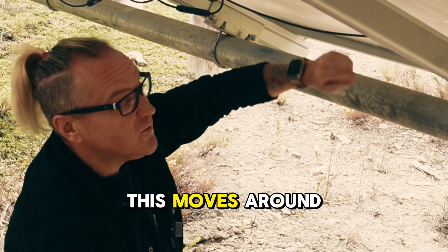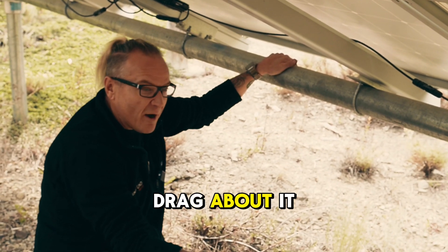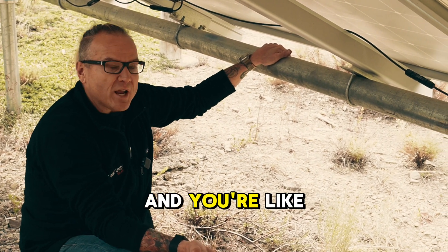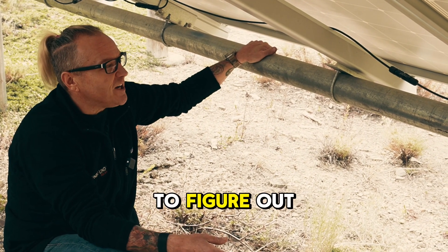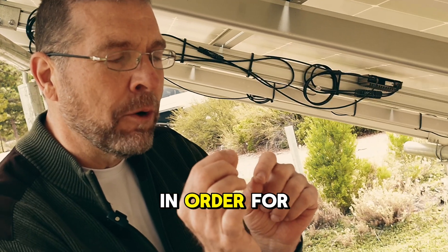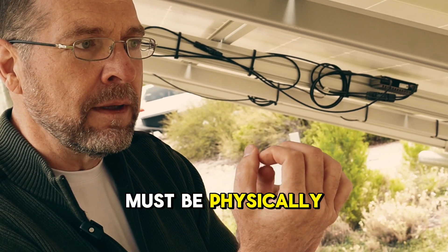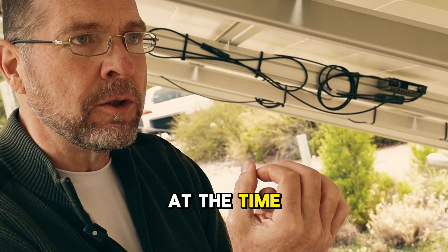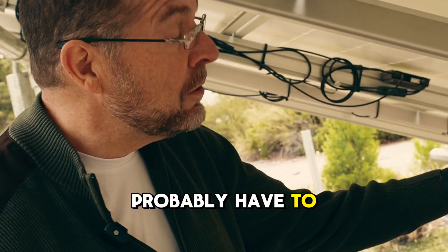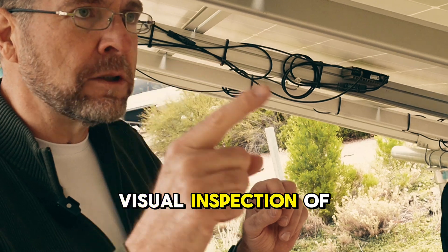It's not through the cable yet, but there is chafing on it. When the wind blows, this moves around a little bit and at some point it's going to fail — and the real drag is it stops functioning and you're trying to figure out where the problem is. In order to diagnose it, that copper conductor inside the insulation must be physically making contact with the rail at the time you're doing your testing to try to isolate it. It's difficult — you'd probably have to do a close visual inspection of everywhere.